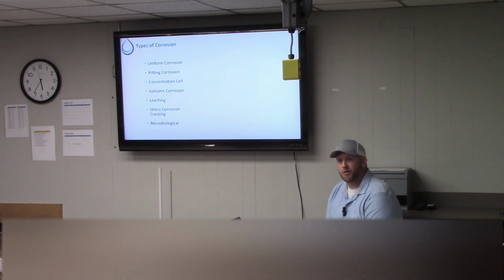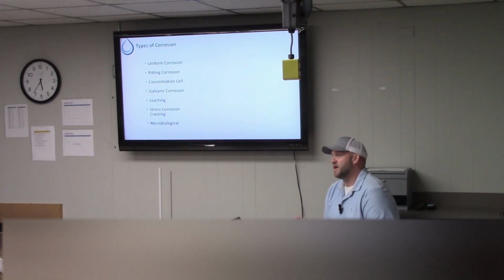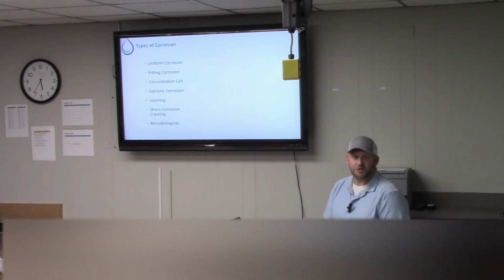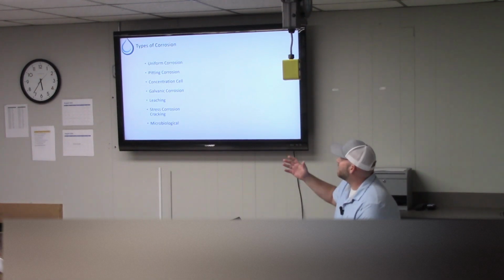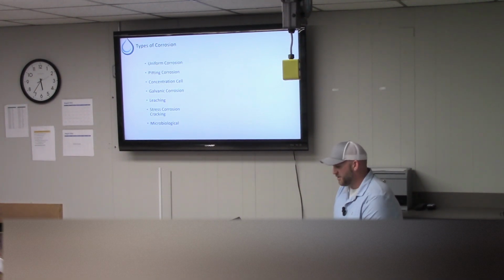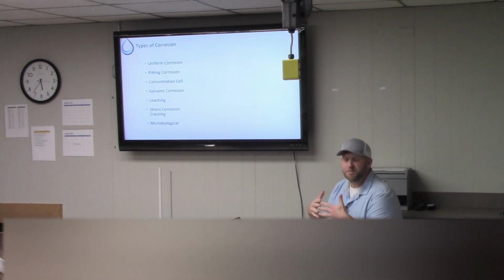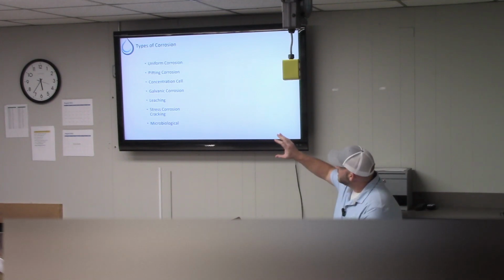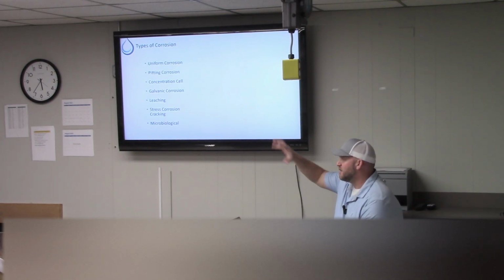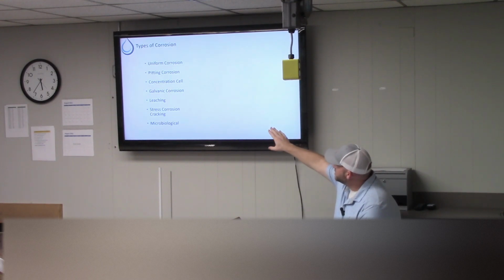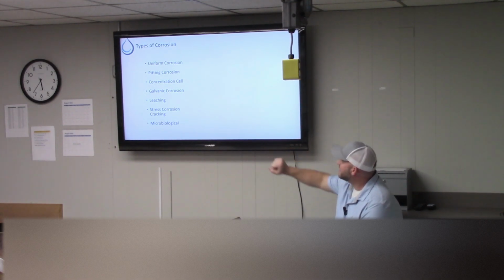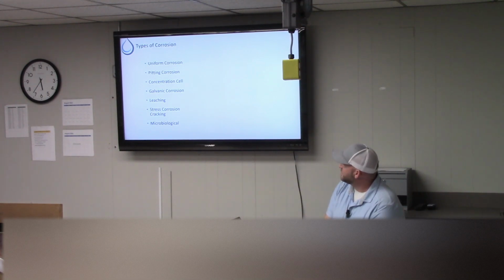These are the types of corrosion you'll probably see the most in a failure analysis report, and the ones you'll notice most if you take down your equipment for inspection. Looking at these systems, uniform corrosion, pitting, concentration cell, and galvanic are likely the ones you'll see most.